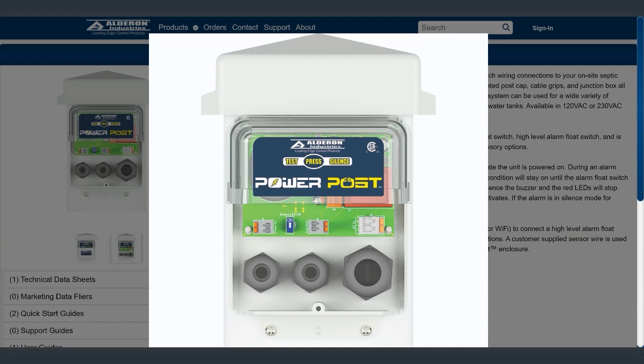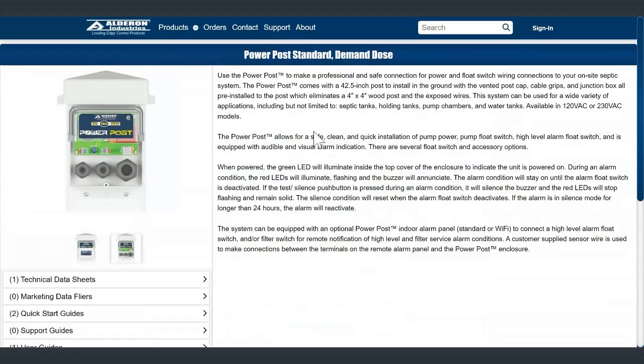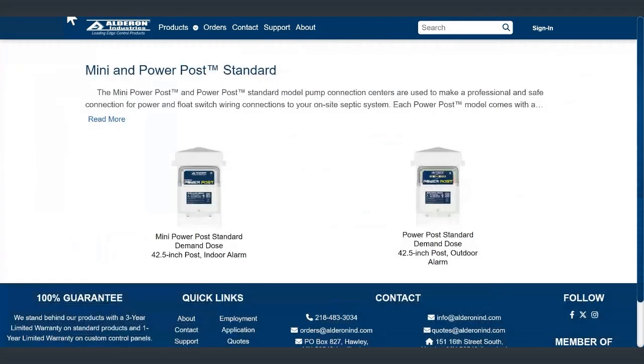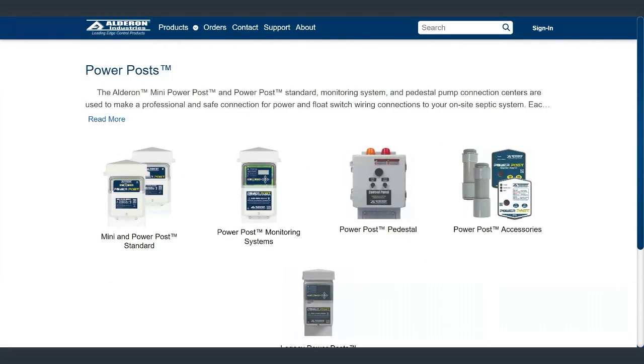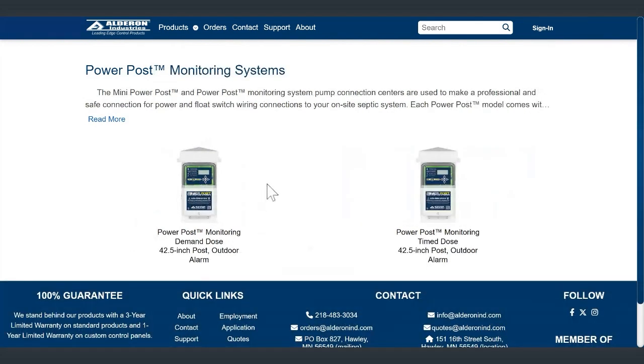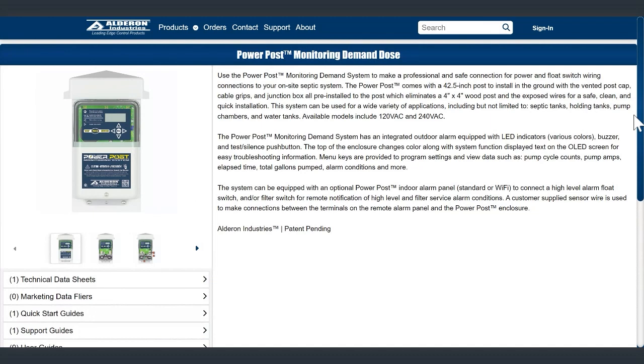So if you use the auxiliary port, you can get the indoor alarm or the outdoor alarm or both. There's a little toggle switch to turn off the outdoor alarm if you don't want to see it outdoors. So that has LEDs built into it, and then a buzzer as well. And then if you go back to our monitoring series, we have two models here. The first one is Demand Dose.